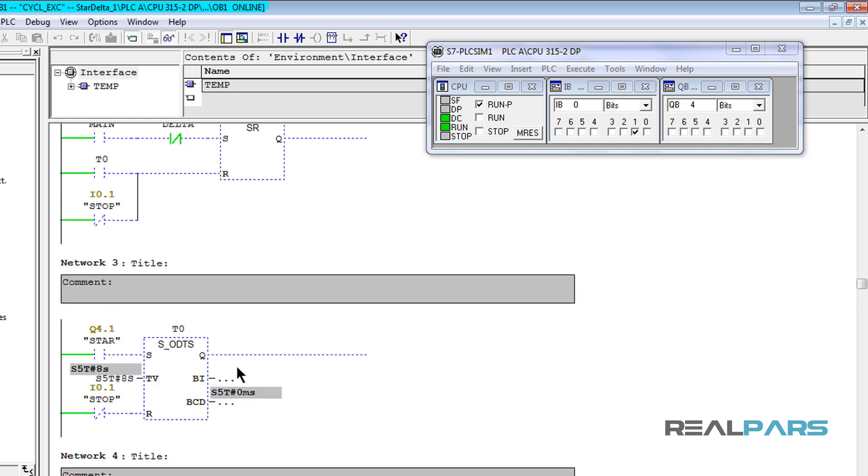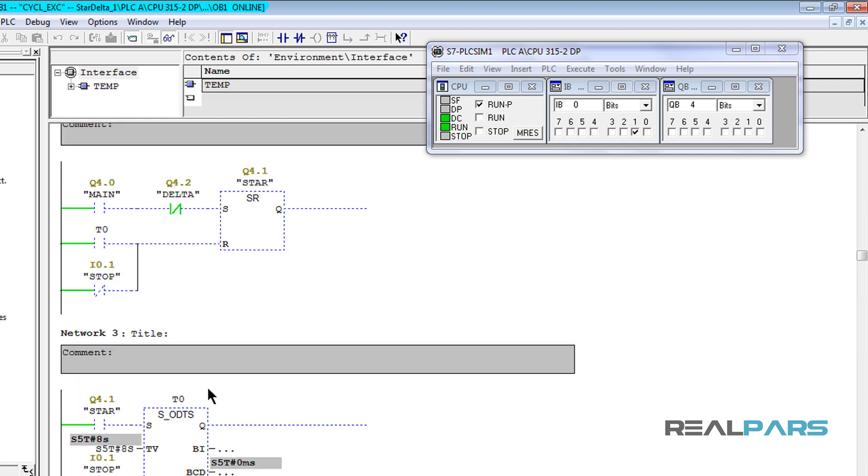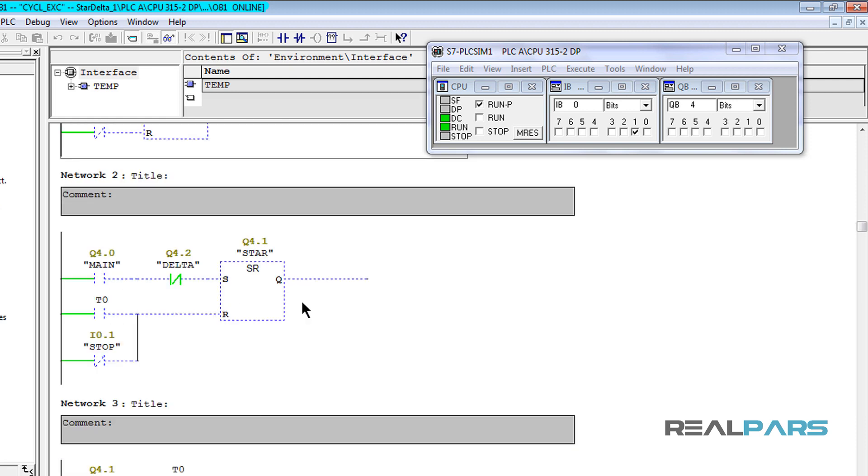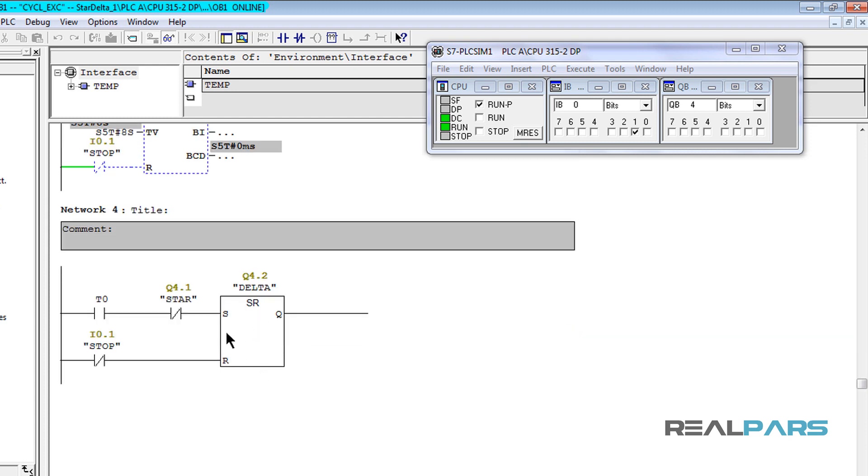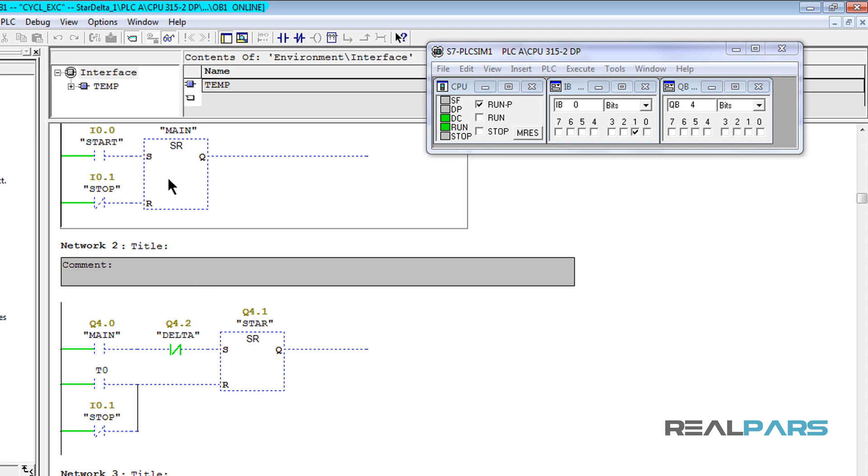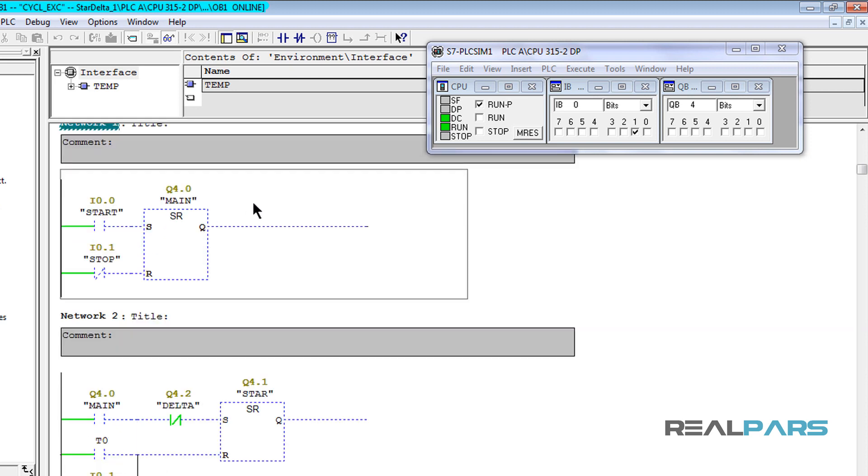And then after an 8 second delay, which is caused by this timer here, the star contactor should be de-energized and the delta contactor should be energized, all while the main contactor is still energized.